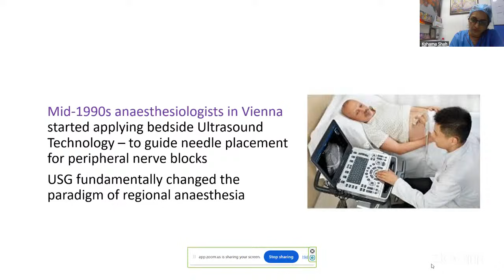So what are the fundamentals of ultrasound guidance? Ultrasound is a device with a probe, the transducer, which generates high-frequency sound waves, generally more than 20 kilohertz, using piezoelectric crystals. The waves propagate through the tissues, as you can see in the picture, and then get reflected back to the transducer. Depending on the time delay and the intensity of the returning wave, a real-time two-dimensional image comes on the screen, and we are able to identify the tissues.